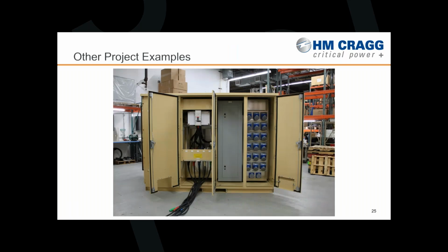What was very unique about this system design was that the locations where this would be deployed had no shore power available. So our primary inputs for the system were two 150 kW gen sets and a third source of six Kubota gen sets that could be paralleled together as a potential backup source if there was an issue with either generator at site. We had to aggregate all these input sources and filter them through automatic and manual transfer switch systems to and from the UPS, to provide a protected power distribution panel for the critical loads at the site.